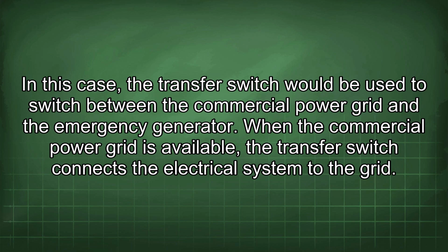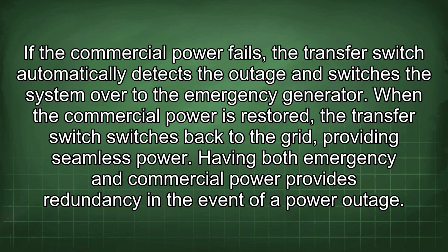When the commercial power grid is available, the transfer switch connects the electrical system to the grid. If the commercial power fails, the transfer switch automatically detects the outage and switches the system over to the emergency generator. When the commercial power is restored, the transfer switch switches back to the grid, providing seamless power. Having both emergency and commercial power provides redundancy in the event of a power outage.